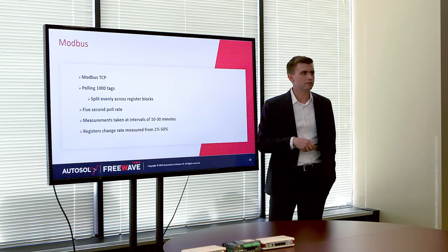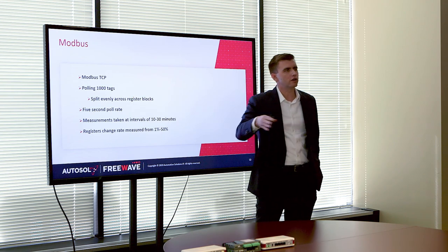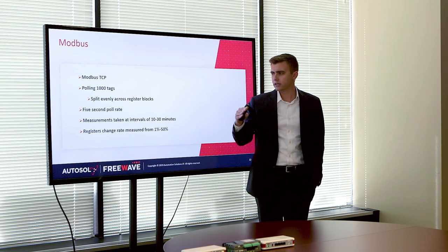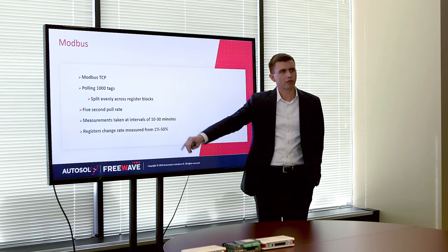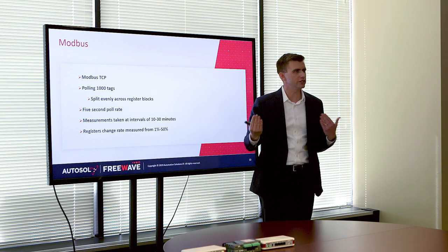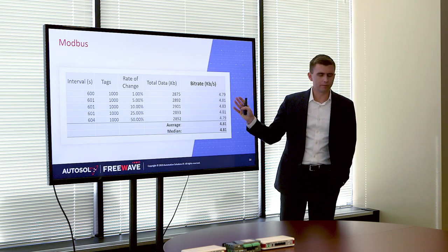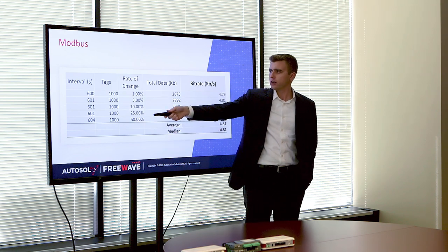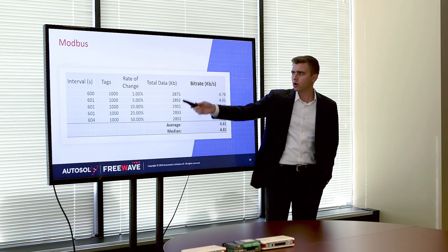The first one we tested was Modbus TCP. We polled 1,000 tags evenly across the four sets of Modbus registers, polled everything at five seconds, and did it at varying intervals between 10 to 30 minutes with varying change rates. So we have 1,000 tags with 1% down to 50% actually changing every five seconds. We have our interval here — 600 seconds, 10 minutes — 1,000 tags, our change rate of 1%, 5%, 10%, 25%, and 50%, and then the total data consumed.